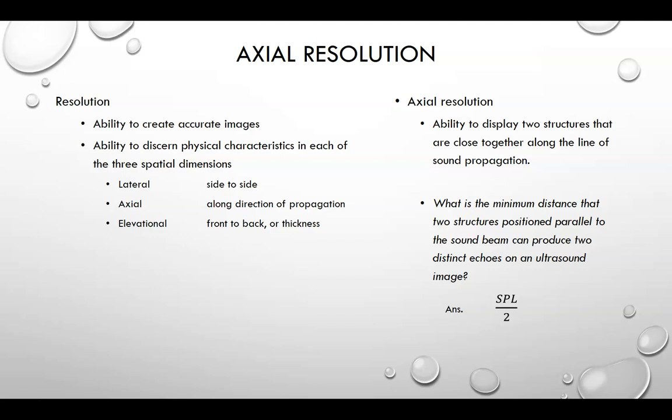Axial resolution is the ability to discern structures along the path of the pulse. Two structures closely together at slightly different depths — if we can discern them apart, we have the axial resolution to do so. Elevational resolution is perpendicular to both axial and lateral, along the thickness of your probe. If you're always incorporating some liver tissue with a cyst and can never separate them in the elevational plane, you will not see the cyst clearly.